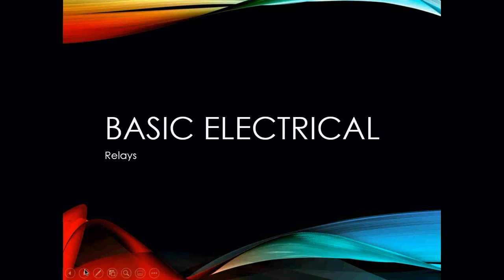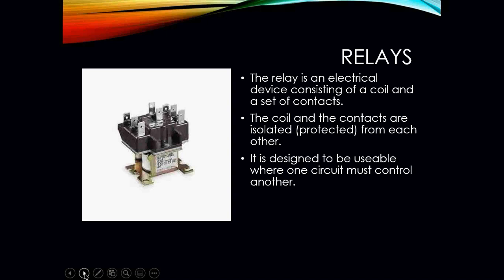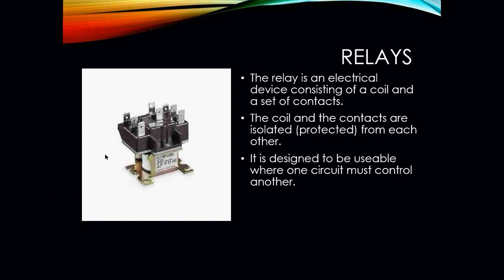So HVAC relays are nothing more than an electrical device consisting of a coil and a set of contacts. Our coil is right here. Our contacts are right here. Okay, the coil and the contacts are isolated from each other. They are protected. The two parts do not touch in any way. However, they are designed to be usable where one circuit must control another. So how are we able to do that?